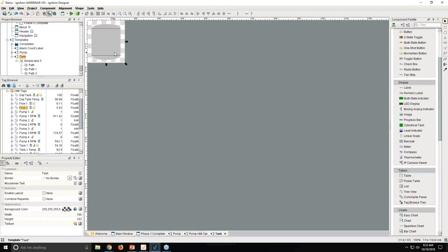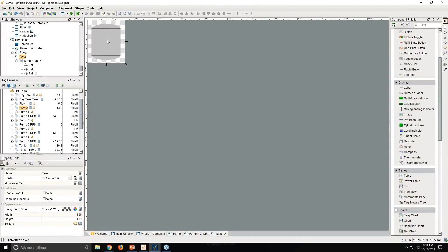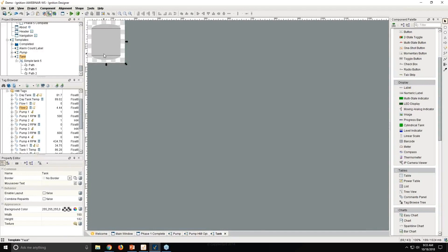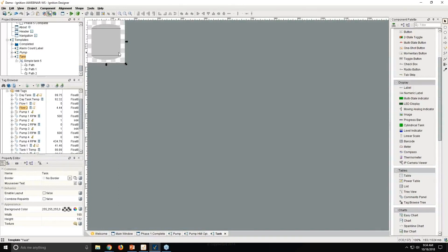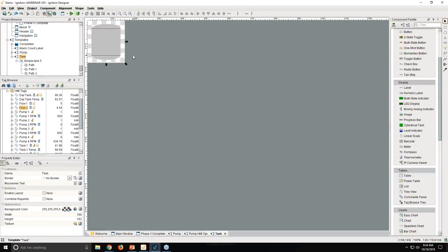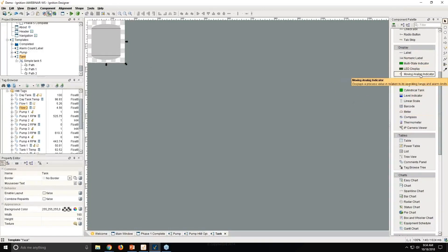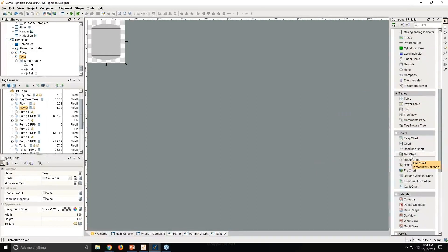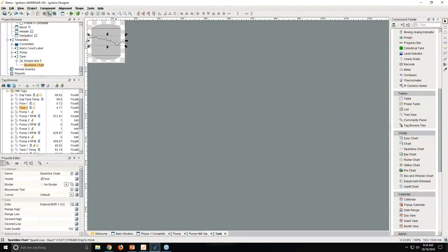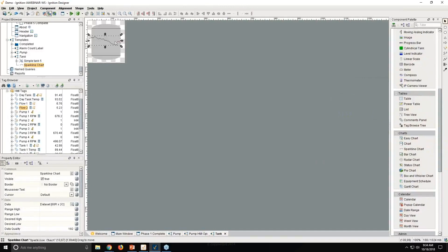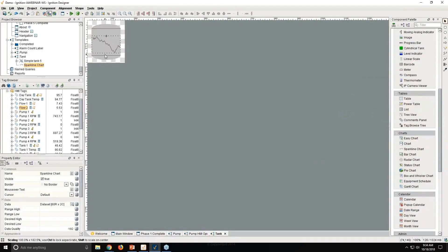So with this, we've got our tank here. What we're going to do now is we want to show the value of this tank. But before we were showing that by showing the liquid in here and showing it go up and down. Rather than doing it that way, what we're going to do is we're going to add a sparkline chart inside this tank so we can see the current value. But you can also see where that value has been over the last 10 minutes. That's the whole idea of adding more information onto the same amount of real estate. Our sparkline chart exists over here in our component palette. If I go down to charts, pull out a sparkline chart, and we will have that take up the full size of the main body of the tank.